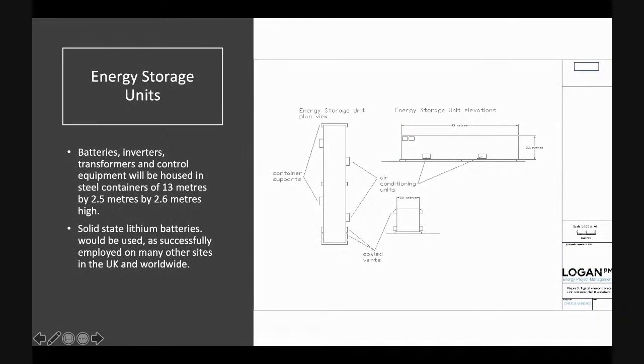The energy storage units themselves contain all the batteries like I'd explained - racks and racks of smaller batteries, inverters inside them, transformers, all the equipment we need. Those units are 13 metres by 2.5 metres by 2.6 metres high. The batteries we're using are solid state lithium batteries, which have been used successfully on most other battery projects in the UK and worldwide - it's proven technology.